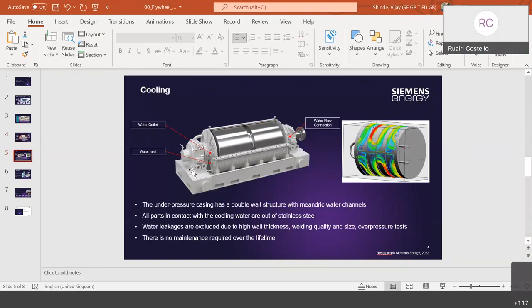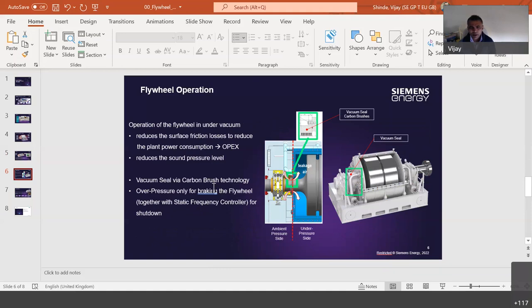On the next slide, you see how the cooling is also done with the water flow connection. There is water running in a meander water channel fashion, and the cooling water system is made of stainless steel. All parts which are in touch are made of stainless steel. There is no water leakage possibility. And the interesting fact is that over the lifetime of the flywheel, no maintenance is required. Again, on the flywheel operation, this picture shows how it is operating under vacuum. It reduces the sound pressure level. It also reduces the friction losses and so there is less OPEX. Also, there is a vacuum seal in the picture here with the carbon brush technology. And we also need to understand that overpressure is only for braking the flywheel, together with the static frequency controller for shutdown.